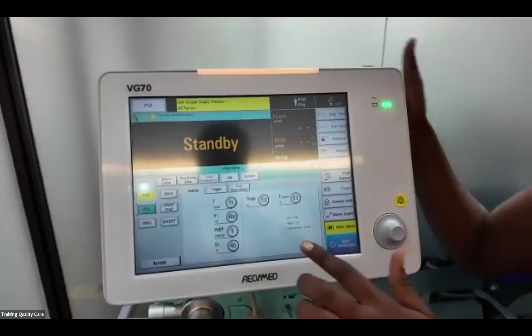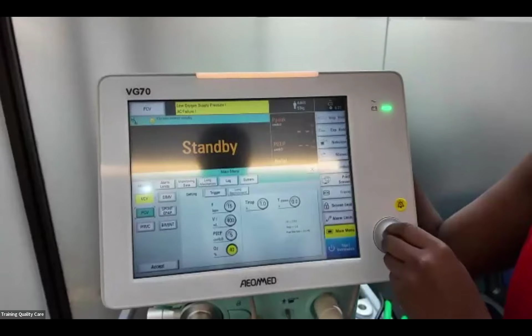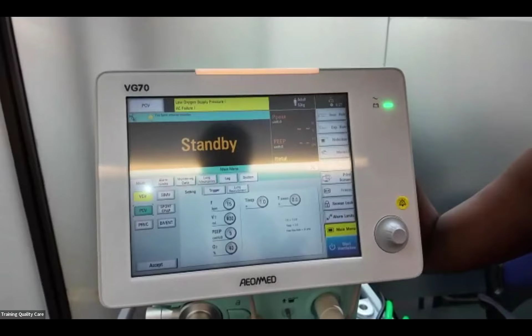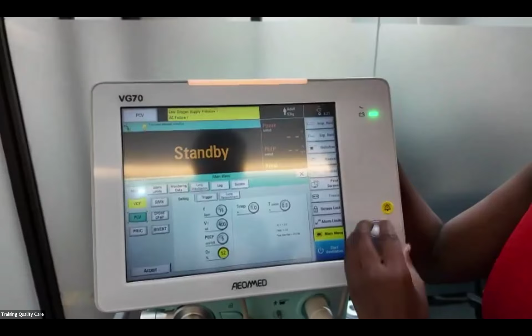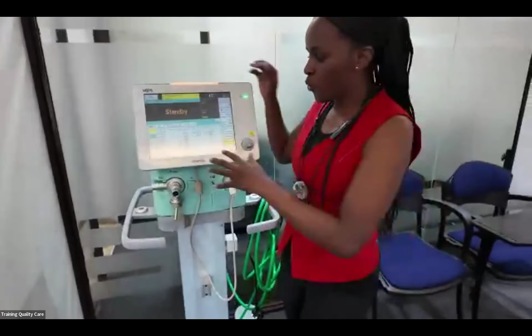And now here I have the settings. The first setting that we talked about is the FiO2, and that is the universal setting, the percentage of oxygen. Now, to begin with, once I have intubated my patient and just want to start ventilating the patient, you want to start at 100% FiO2. So I'll move to 100% and accept. Now, PEEP, positive end expiratory pressure. The pressure at the end of expiration. You want it to be physiologic.